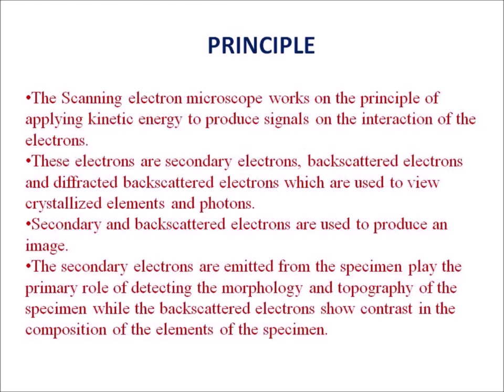When we examine the principle of scanning electron microscope, it applies kinetic energy to produce signals on the interaction of electrons. These electrons are called secondary electrons, backscattered electrons, and diffracted backscattered electrons, and are used to view crystallized elements and photons. Secondary and backscattered electrons are used to produce an image. Secondary electrons emitted from the specimen play the primary role of detecting the morphology and topography of the specimen, while backscattered electrons show contrast in the composition of the elements of the specimen.